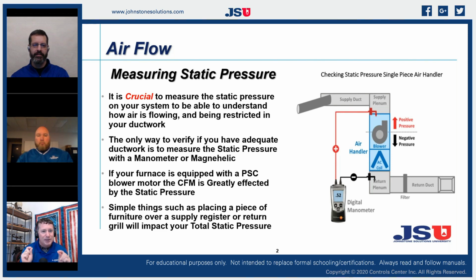And as soon as we started taking the covers off the front of the filter, we found the plugged 1-inch filter that the installers put in the system when it was originally installed. So it had a 1-inch filter that was plugged solid, and it had that 4-inch media filter, but the static pressure wasn't showing up because the static pressure was behind the 1-inch filter.